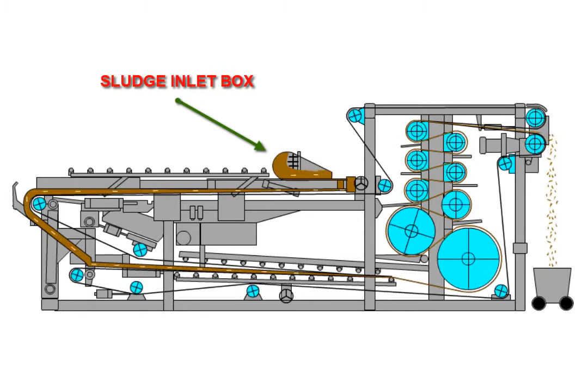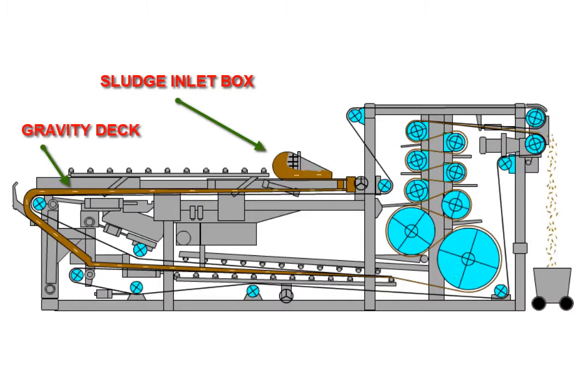Wet sludge enters onto the press through a sludge inlet box where it is gently dispersed and spread evenly. Sludge is spread evenly along the gravity deck by a sludge leveling bar and passes through a series of plows, aligning the sludge into rows allowing the free water to cascade off the sludge through the belt.